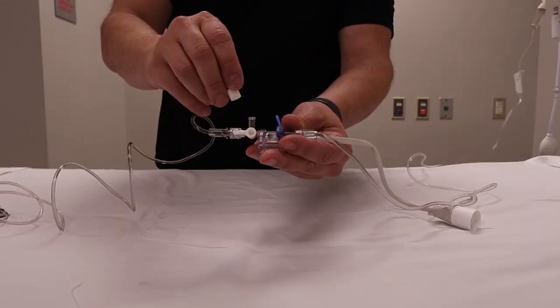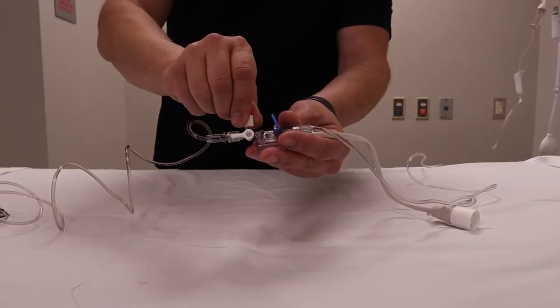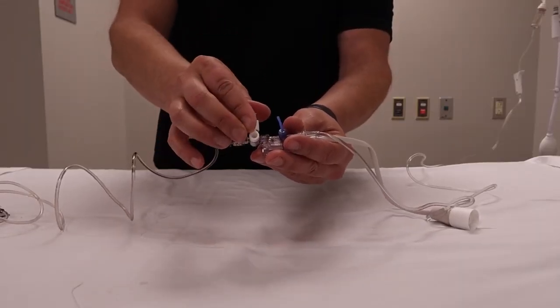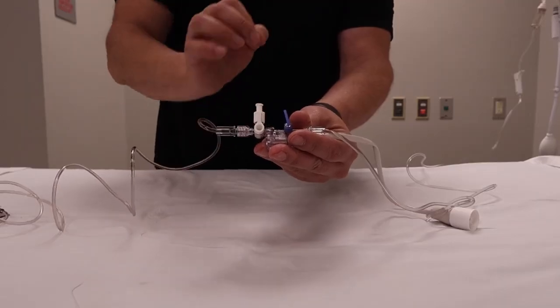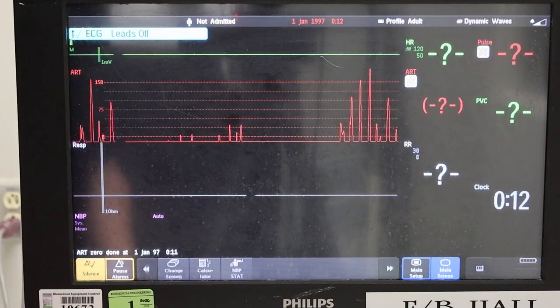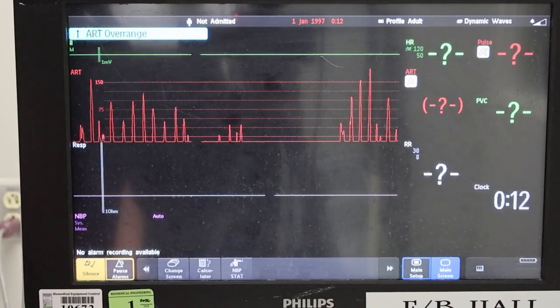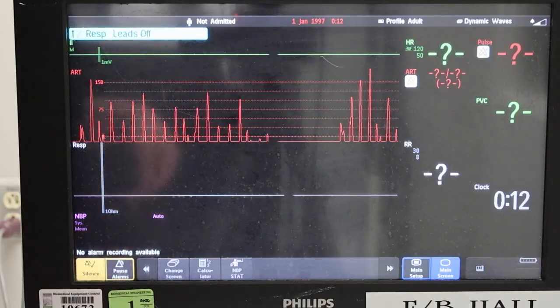Once the zero is complete, replace the cap onto the open port and move the stopcock to the up position to open the system to the transducer. If all steps have been done correctly, you will start to see a cardiac tracing, and a blood pressure for the arterial system will be displayed.